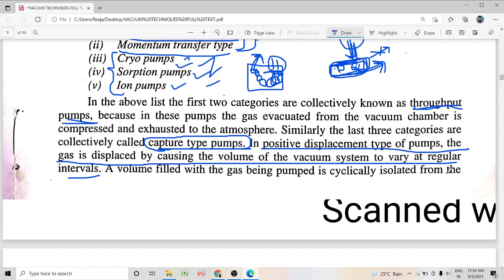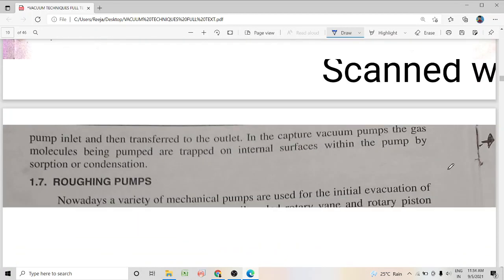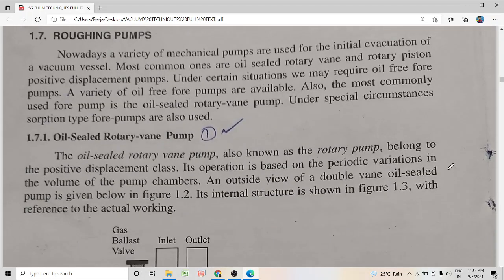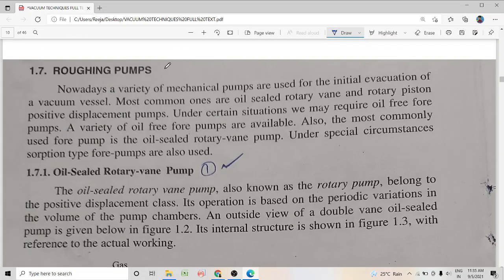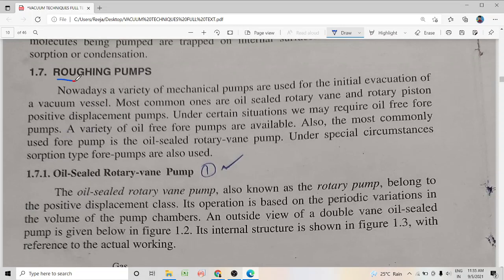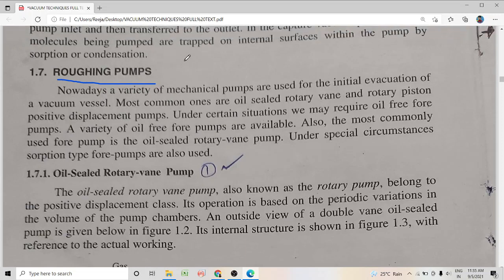Now let us go to our study of the first pump. Before learning our first pump in detail, let us revisit what forepumps are. Forepumps, or roughing pumps, are pumps which are used to initially evacuate a vacuum vessel so that the pressure in the vacuum vessel becomes suitable for the operation of a high vacuum pump or a fine vacuum pump.